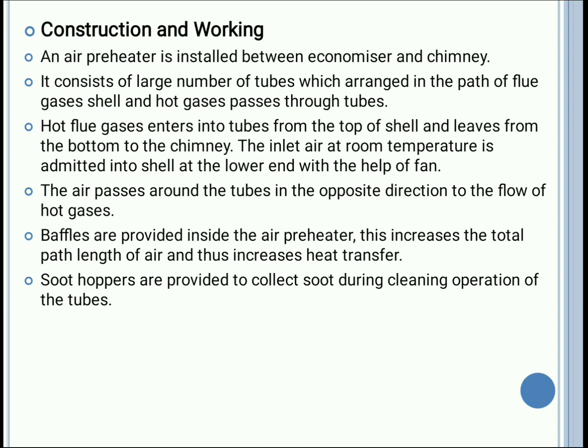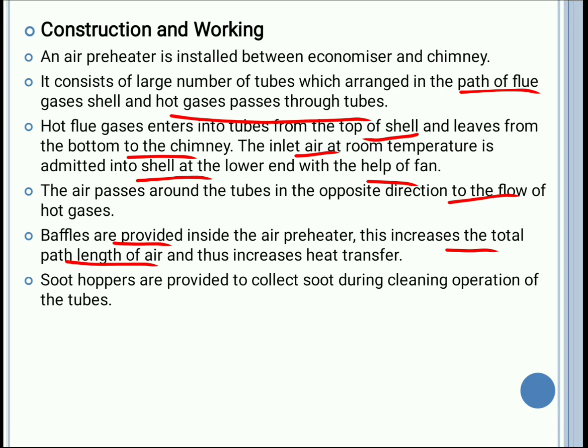An air preheater is installed between the economizer and the chimney. It consists of a large number of tubes which are arranged in the path of flue gases, and the hot gases pass through the tubes. The hot gases enter into the tubes from the top and leave through the bottom, whereas the inlet air enters at the lower end with the help of a fan. The air passes around the tubes in the opposite direction to the flow of hot gases. Baffles are provided inside the air preheater, which increases the total path length of air and thus increases the rate of heat transfer. Soot hoppers are provided in order to collect the soot.